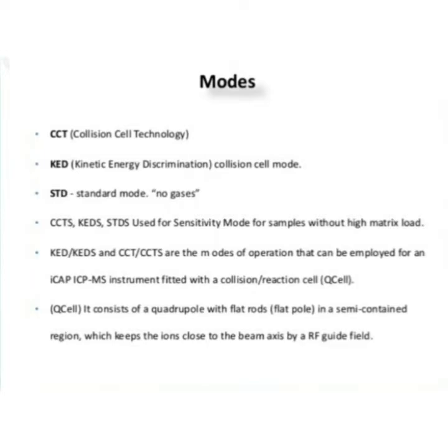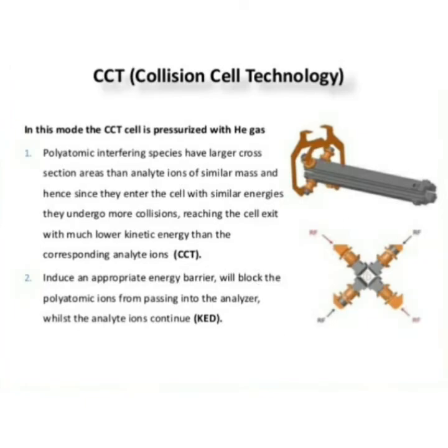KED and CCT are the modes of operation that can be employed for an ICP-MS instrument fitted with a collision reaction cell, the Q cell. The Q cell consists of a quadrupole with flat rods, a flatapole, in a semi-contained region which keeps the ions close to the beam axis by an RF guide field.